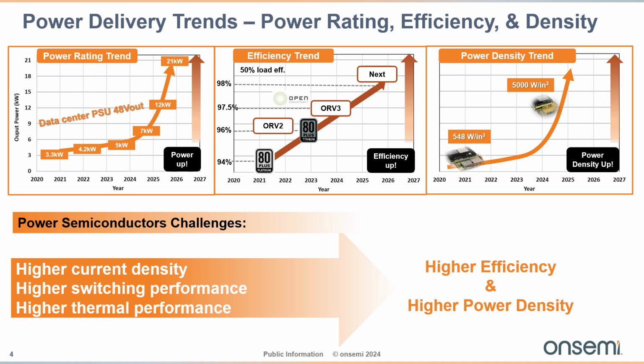Secondly, efficiency is the most important metric here. Until a year ago, industry was targeting 80 plus titanium standard with a 50% load efficiency of 96%. However, we are now targeting 97.5% efficiency at the same 50% load. This is under OpenRack version 3. Moreover, under extreme AI loads, which could be up to 150% load for a fraction of time, efficiency and thermal performance should be acceptable. Solutions that offer high current density, higher efficiency, and are thermally superior will address these needs well.